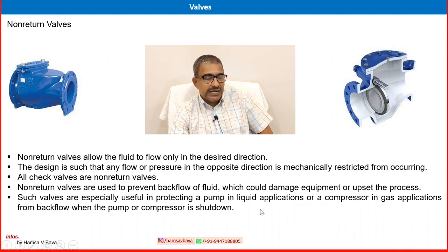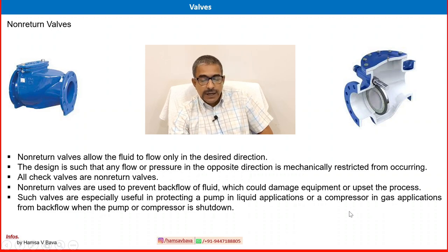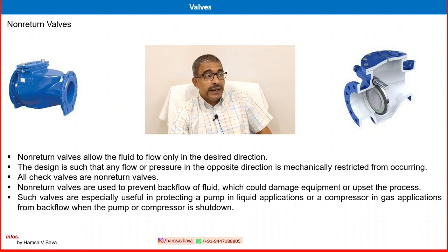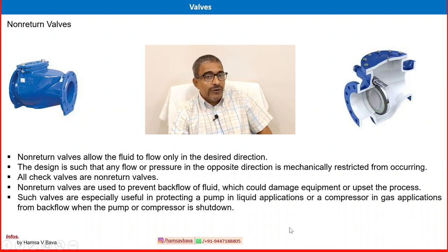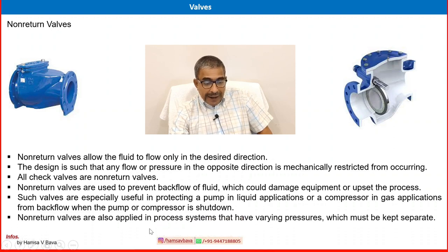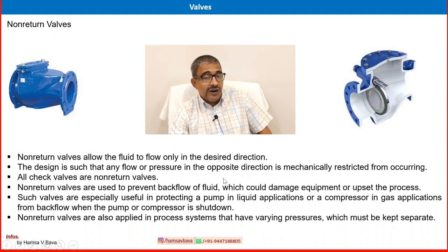Non-return valves are used to prevent backflow of fluid which could damage equipment or upset the process. They are especially useful in protecting a pump in liquid applications or a compressor in gas applications from backflow when the pump or compressor is shut down. Check valves are used in many process applications; two examples are the discharge side of a pump and the discharge side of a compressor. I request you to visit your operational field, refer to the P&ID, find the check valve symbol, and see where and why it is provided.